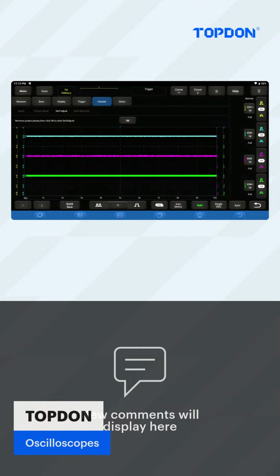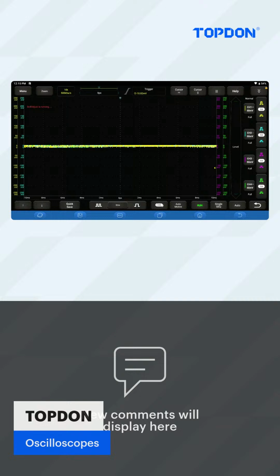Now, what does it do? What it does is it baselines all of the channels on the scope and it zeroes them out properly. So it's going to make sure that there's no issues with the zero setting on each of the individual channels. When we do this, we want to make sure all of the probes are disconnected, and then we're going to use the self-adjust function.